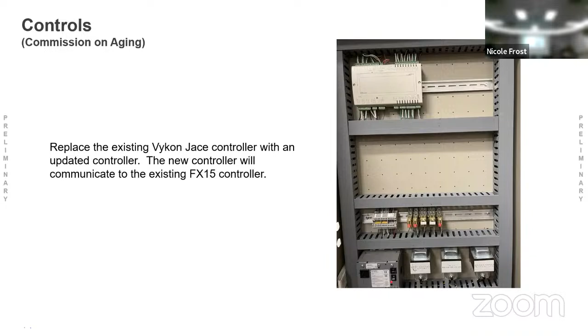Over at the animal shelter, right now you just have regular residential thermostats serving the equipment - 8 furnaces, a combination of furnaces, unit heaters, and makeup units. We're replacing those 8 thermostats and putting in a little network controller, hardwiring the new thermostats in, so everything can be seen from the main server. There were some hot button items about people wanting certain temperatures or doing things with the system, so now you'll have the visibility to look at that.